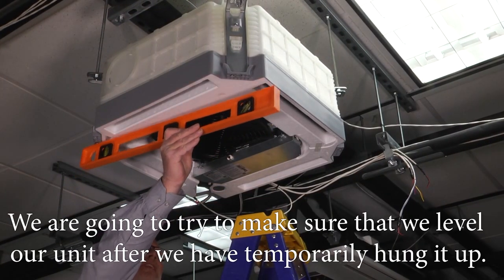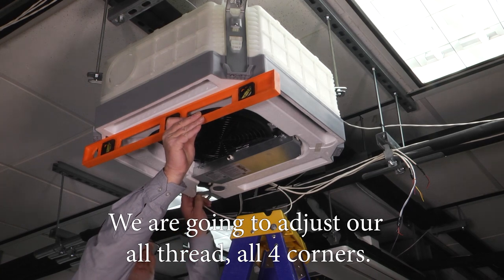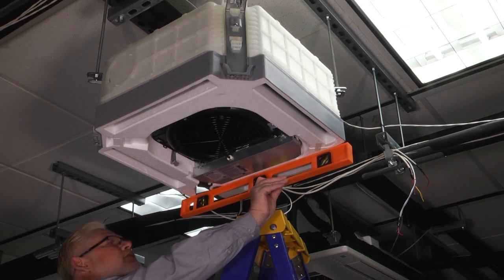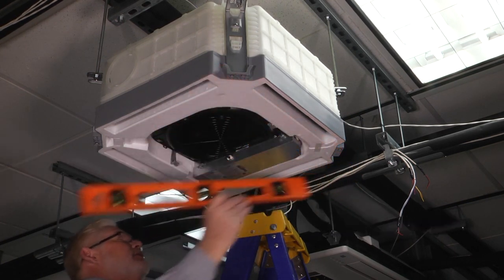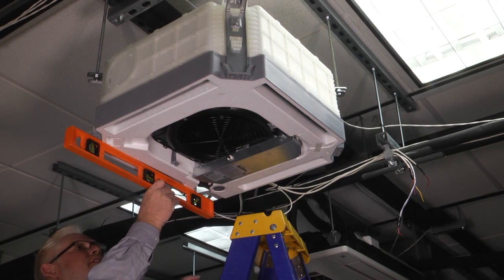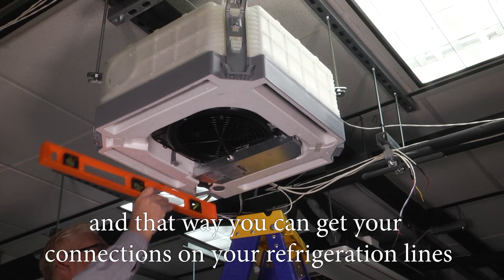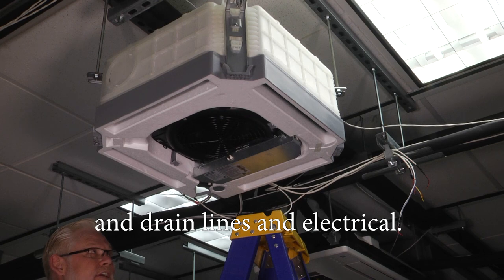We're going to make sure we level our unit after we temporarily hung it up. We're going to adjust our all thread on all four corners. We'll check it front and back on both sides. Make sure you check it from left to right on both sides and verify that it is level before you proceed, and then you can get your connections on your refrigeration lines and drain lines and electrical.